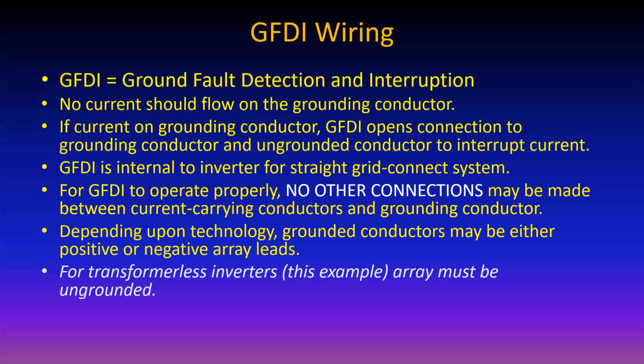how the GFDI operates properly, and the idea that you just don't connect anything on purpose to ground, because that's the grounding. The grounded conductors are connected to the grounding conductors at only a single point. You need single point grounding, and that is generally done through the GFDI device. So you don't ground the green wire to the white wire or whatever anywhere along this system. You let the GFDI device take care of that.